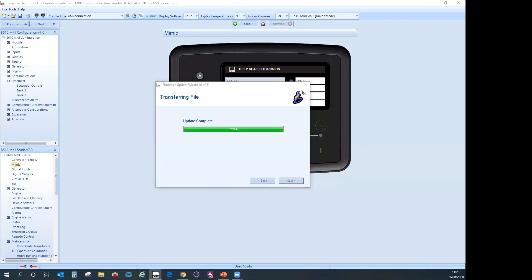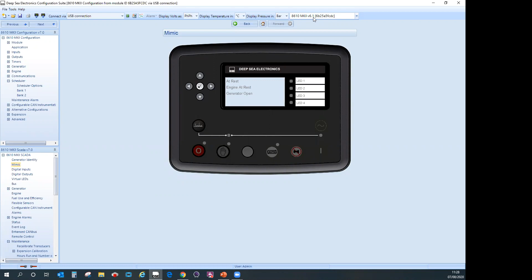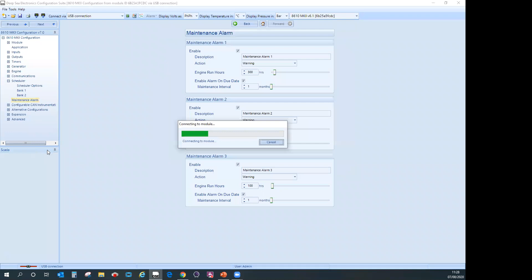Okay, so my update's now done. And if we look on here now, we are reading 8610 Mark II version 6, so it's version 6.1. What's actually happened now is I've updated the firmware, and that's installed what's called a default configuration file. It's not the one that was in there previously.